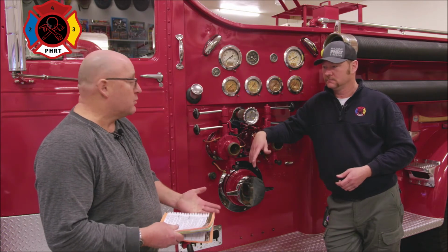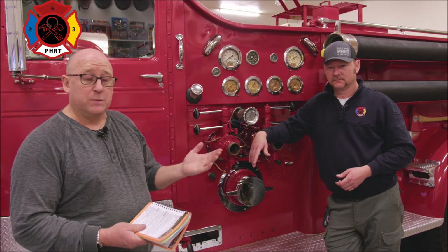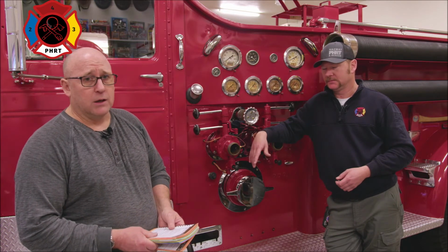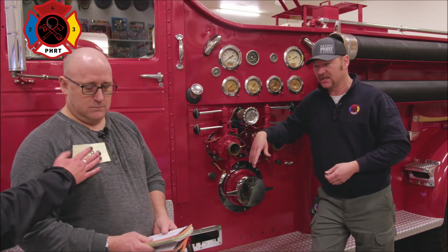But that's where we have to look at the physical properties and preferably the SDS, or look online or do some other research to find out where those vapors are going to go. If the vapor density is less than 1, then they're going to go up into the atmosphere, which is a good thing for us because they disperse quite a bit faster than if the vapor density is greater than 1. It will sink to the ground and pool. It tends to pool up in the low-lying areas. It tends to not disperse quite as rapidly, and it could be trapped within its flammable range and really cause problems down the road. And once again, we have a few of those videos posted up on the newsletter for us as we go through that.